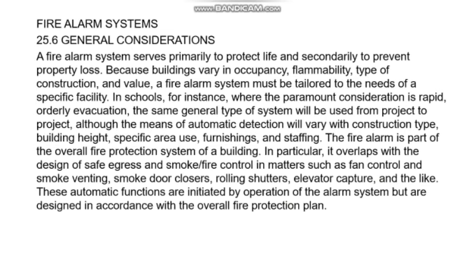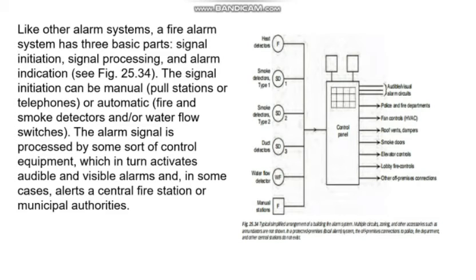Like other alarm systems, a fire alarm system has three basic parts: signal initiation, signal processing, and alarm indication, as shown in the figure. The signal initiation can be manual, like pull stations or telephones, or automatic, like fire and smoke detectors and water flow switches. The alarm signal is processed by some sort of control equipment, in the figure, the control panel, which in turn activates audible and visible alarms and in some cases alerts a central fire station or municipal authorities.